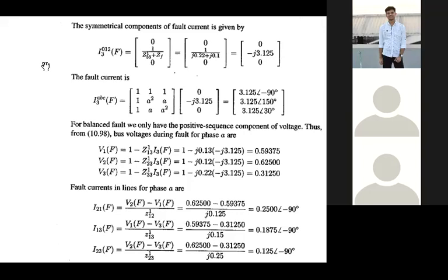Likewise, for short circuit or fault current calculation, if you apply the Thevenin concept, you can do that, but it has some limitation. That means up to a certain limit you can do that by the Thevenin concept or equivalent circuit. But when you move to a large circuit, it will be better to shift that idea to the bus building concept, Z bus. From Z bus, you can find the fault current.